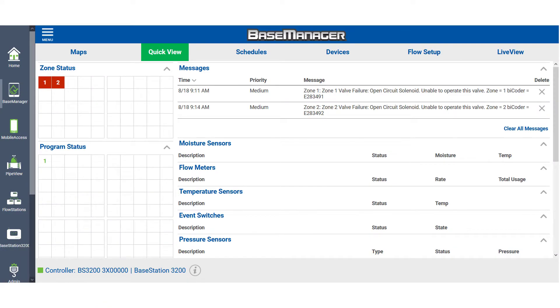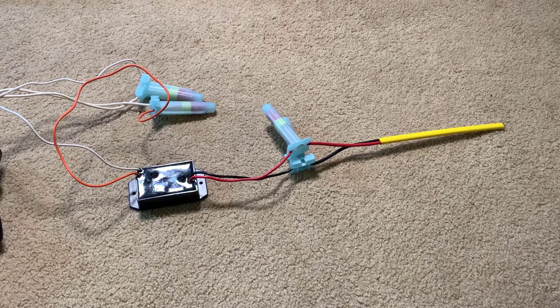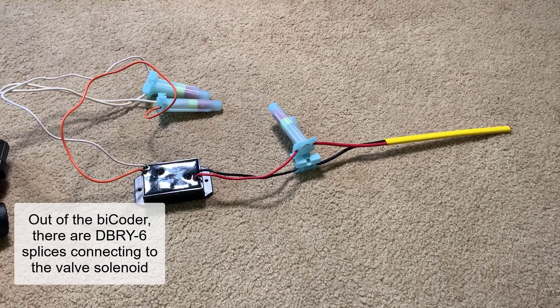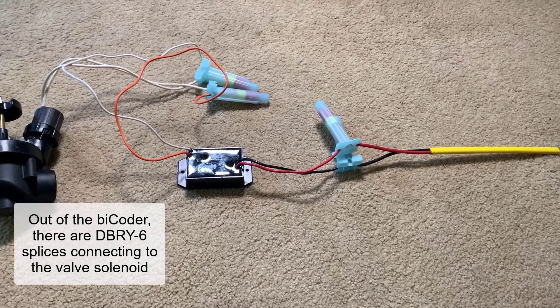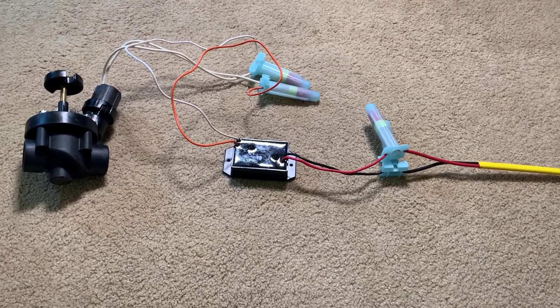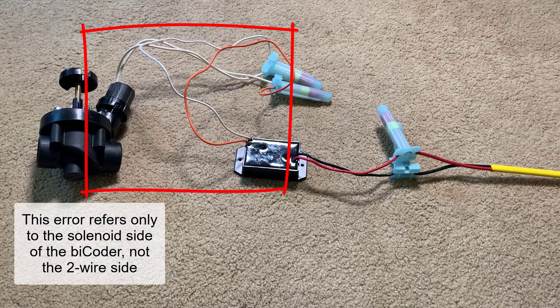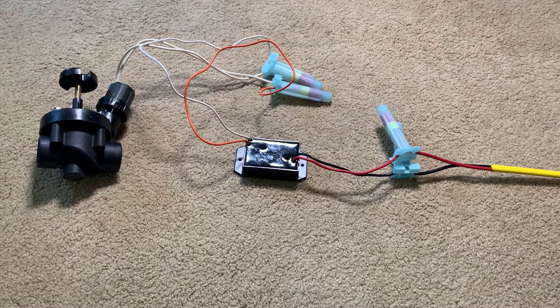Before we talk about the causes, let's review the parts that are involved. Coming in, we have a two-wire path with DBRY6 splices connected to the bicoder. Going out of the bicoder, there are DBRY6 splices connected to the valve solenoid. This error refers only to the solenoid side of the bicoder, not the two-wire side.